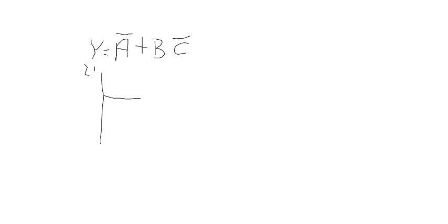The top branch is just going to have A not. And I don't write the not there because the normally closed contact takes care of that for me. And then OR that with B, which is normally open since it's not inverted, and series gives me the AND.